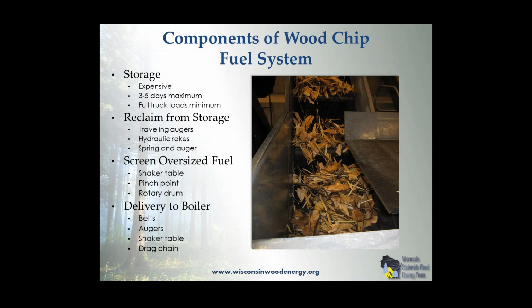Every project we've ever done, the owner says, oh, I would like a month's worth of storage. I think that's where it probably starts, and practically that's just not going to happen because he can't afford that live bottom floor, that kind of storage. And our advice to folks is, look for 3 to 5 days of storage when peak demand hits and you're in the right ballpark. Make delivery of the fuel not your problem. Make it the problem of the person supplying your fuel.